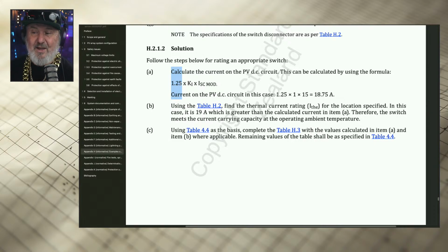So that means irradiance is proportional, current from a PV array is proportional to irradiance. So you're going to get a lot more oomph, a lot more current coming out of your panels at higher irradiance. So that's what the 1.25 times safety factor is. And it's nothing new, actually.